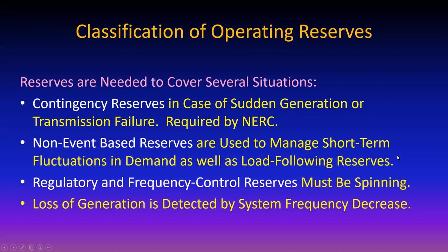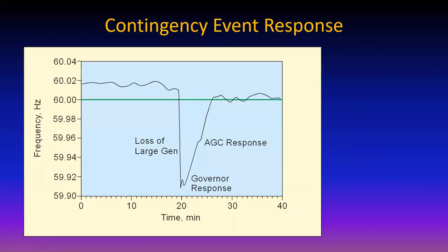So it's fairly straightforward what has to be done. Here's a situation: if we lose a large generator, then the governors on the other generators notice that, oh my goodness, now there's demand for a whole lot more electricity, so we're going to have to kick in a little more fuel to deliver more torque so we can deliver more angular velocity and get our speed back up so we can produce up to our rated response.